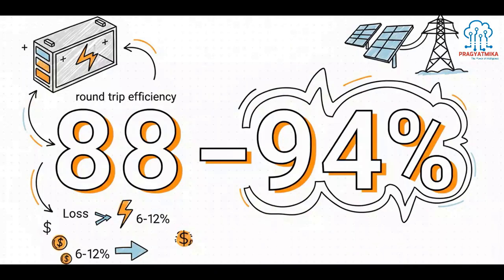So what's a normal rate here? For modern lithium iron phosphate utility arrays, a healthy round-trip efficiency typically sits somewhere between 88 and 94%. Think about that for a second - that means in a best-case scenario, you are instantly losing 6 to 12% of the energy you paid for every single time you cycled the battery.